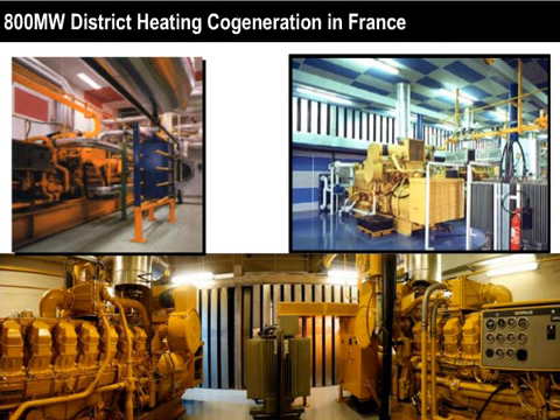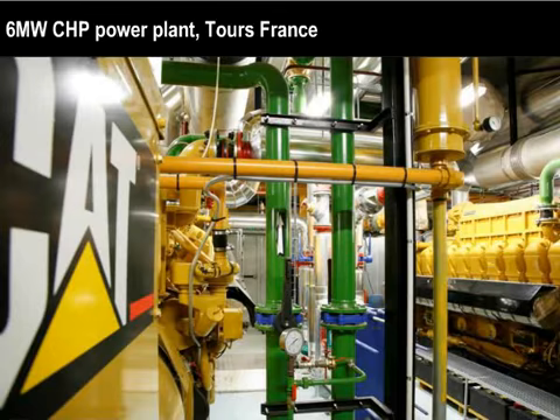Caterpillar has over 800 megawatts installed in district heating CHP applications in this country, and I'll have an example here. This is a nice 6 megawatt power plant built out of our 2 megawatt units, or 3 units, and you can see a lot of pipes because these guys don't want to lose a watt, and they want to capture all the heat, and they have pipes and heat exchangers on all circuits they can find useful.